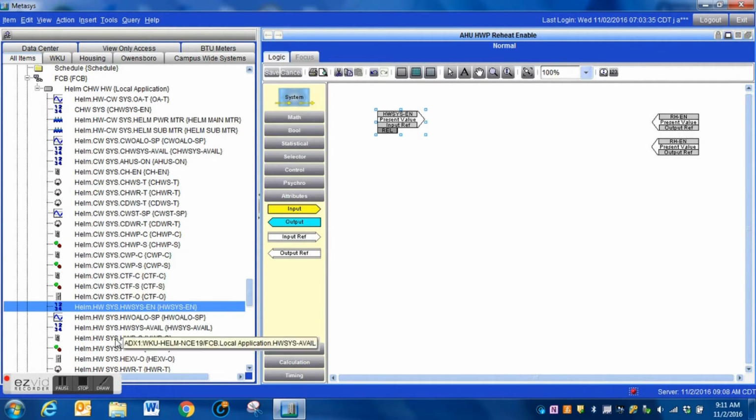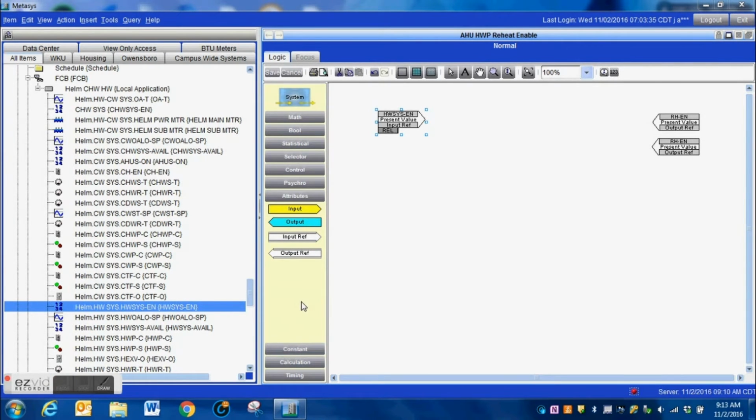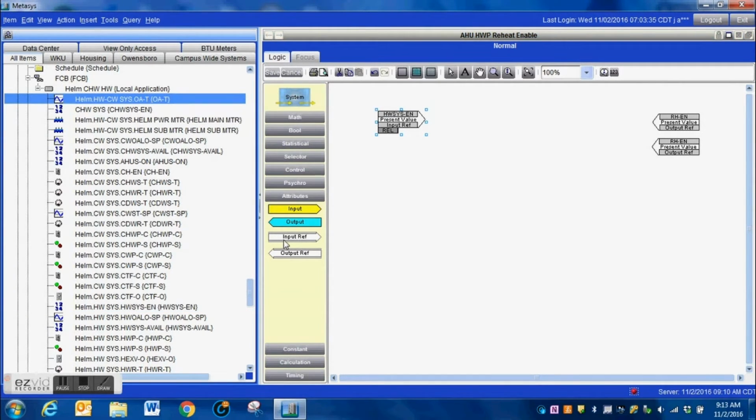And you know, LCT, if you're not very familiar with it, is a very powerful tool within Metasys Extended Architecture. You can do a lot with this. Now, I will warn you that LCT is a memory hog. It uses a lot of system resources and can bog down your NAEs and NCEs if you try to do too much control in the NAEs and NCEs. It's better off to keep as much control as possible within the individual controllers.